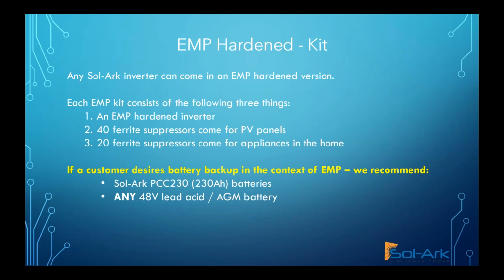If a customer desires battery backup in the context of EMP, we recommend lead acid or AGM. And the reason we recommend lead acid or AGM, I touched on earlier, is just because there's nothing there that's going to be susceptible to an EMP. You've got the plastic case, you've got the lead or the carbon plates in the battery, you've got the electrolyte solution, you've got a cap on the top of the battery, and you have a positive and negative terminal. That's it. What's going to be susceptible to an EMP in the battery world is going to be the battery management system, the motherboard on top of the battery that's running the BMS and has all that circuitry, etc.